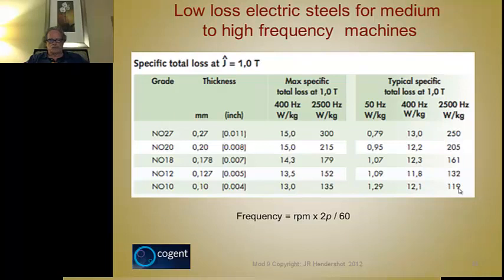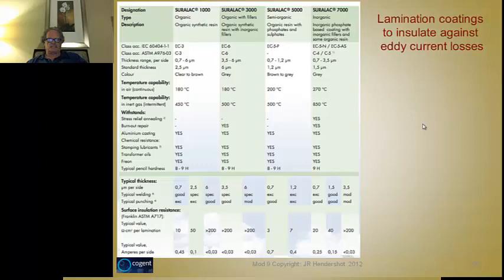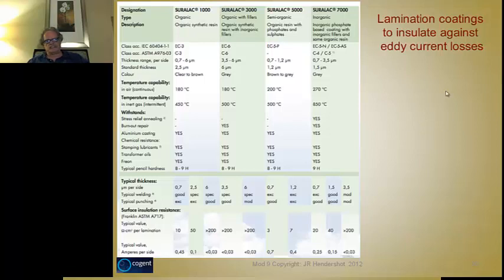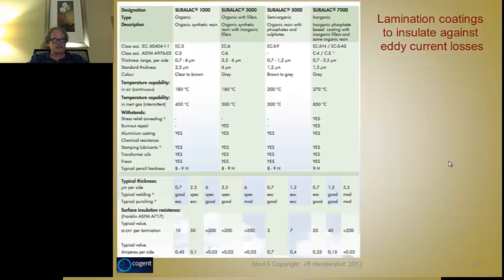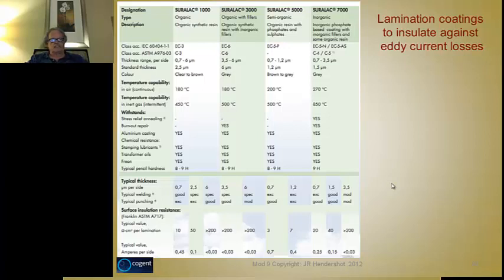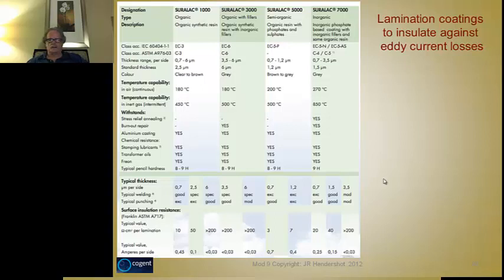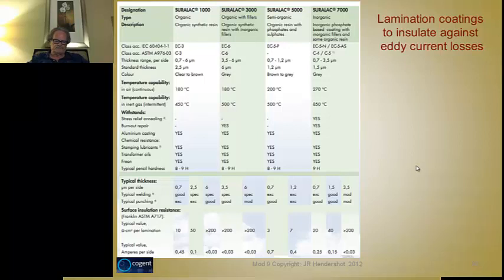One of the things that helps reduce core losses is coating the laminations with insulation material — very thin layers. It can't be too thick or it interferes with the flux-carrying capacity of the core. You don't want much of the axial length taken up by insulation material since you can't get flux through it — but it does insulate against eddy currents. These coatings are applied to only one surface of the lamination, so when you stack laminations in the same direction they come out of the die, you have one insulation coating between any two adjacent laminations. Be careful not to flip them over.